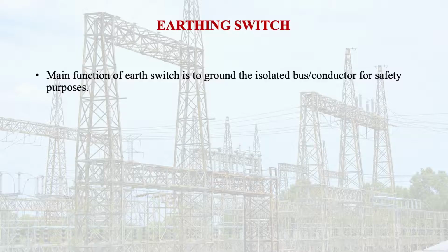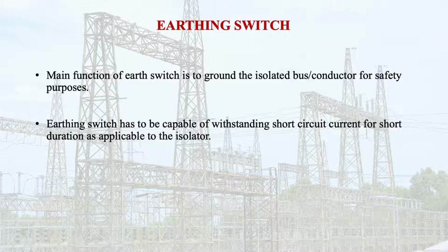Why? Do you know about this? What is the use of the earthing switches or earthing arrangement in case of any fault? The main function of the earth switch is to ground the isolated bus or conductor or equipment. The earthing switch has to be capable of withstanding short circuit current for a short duration, as applicable to the isolator.